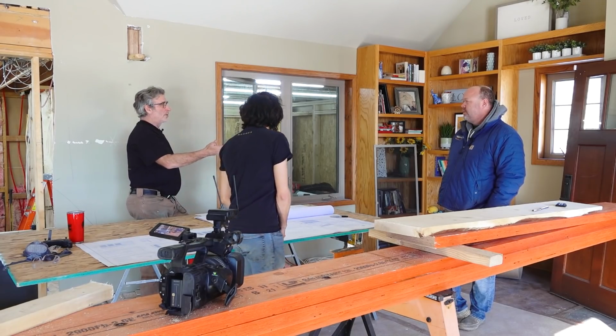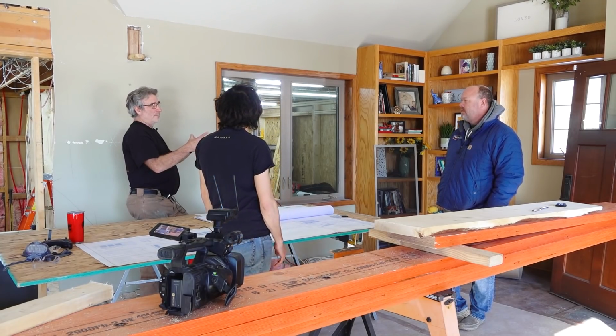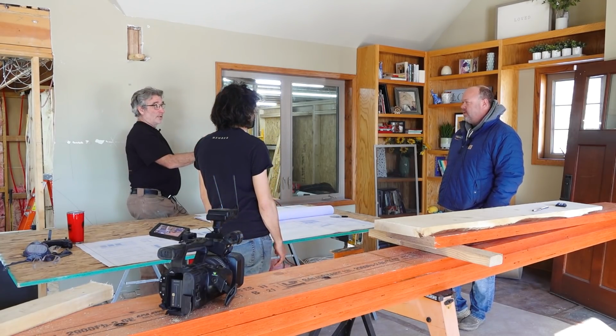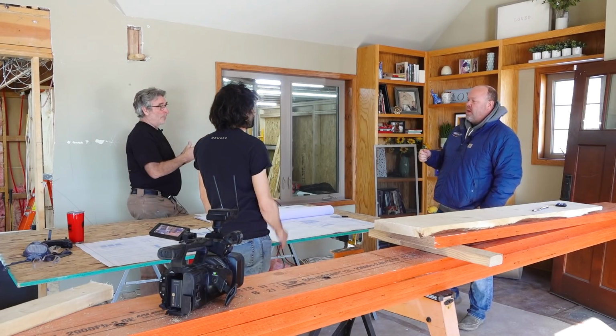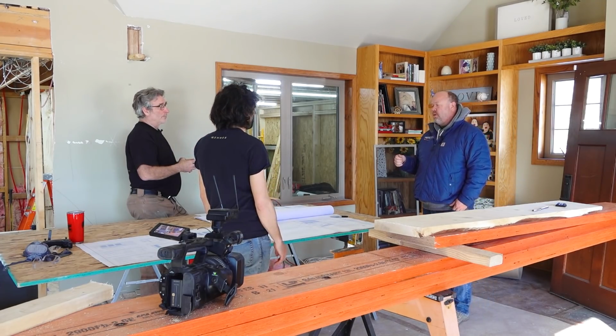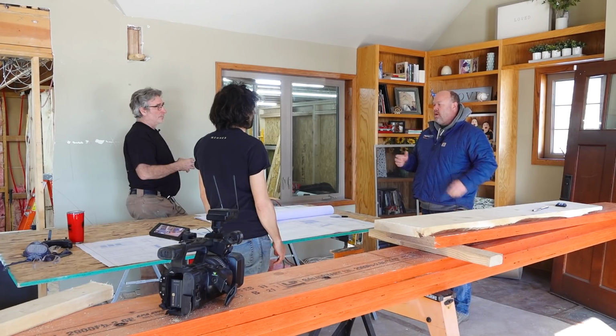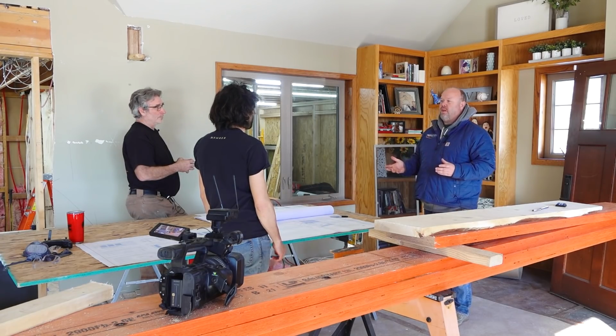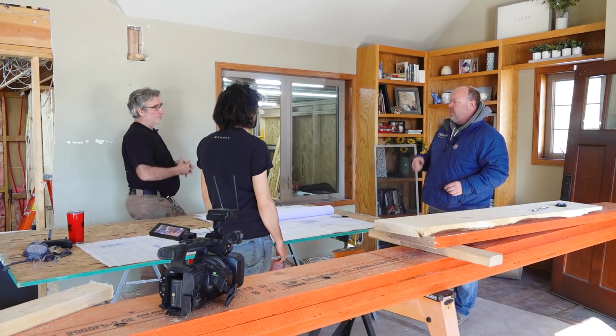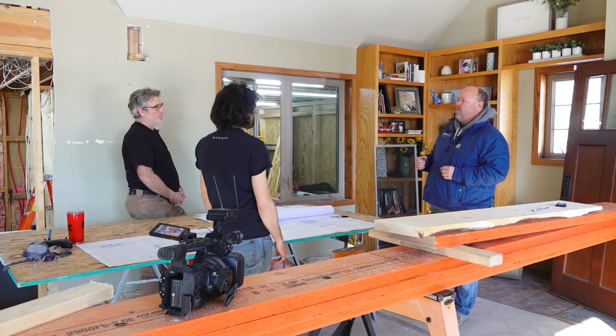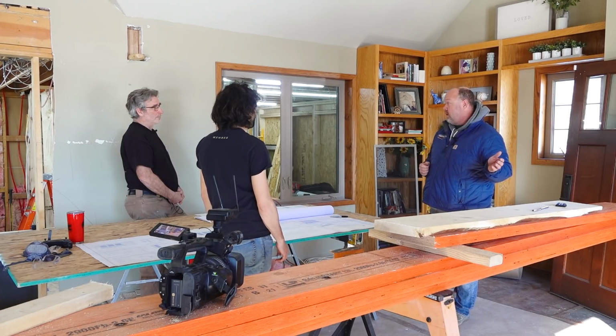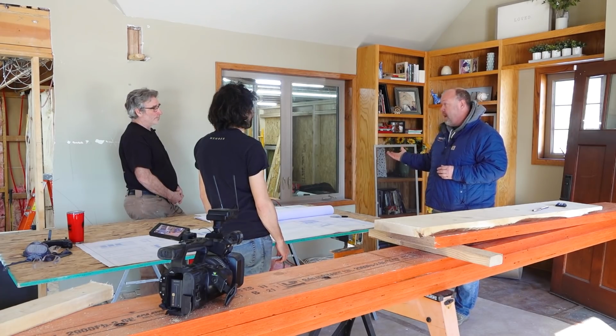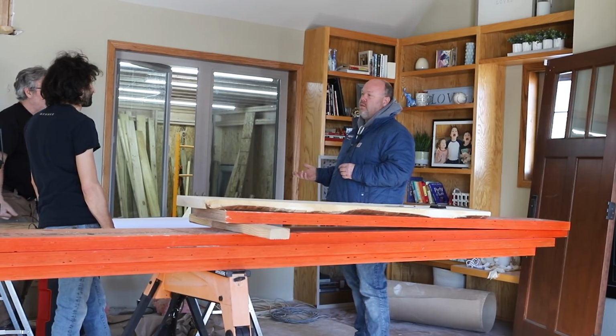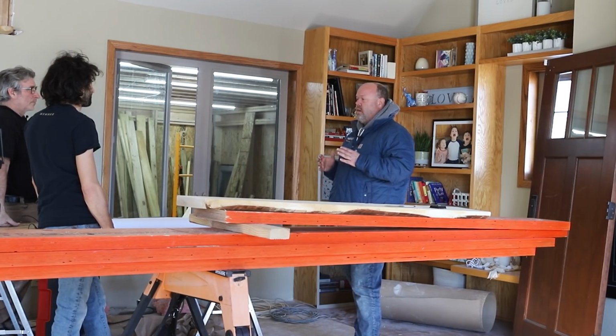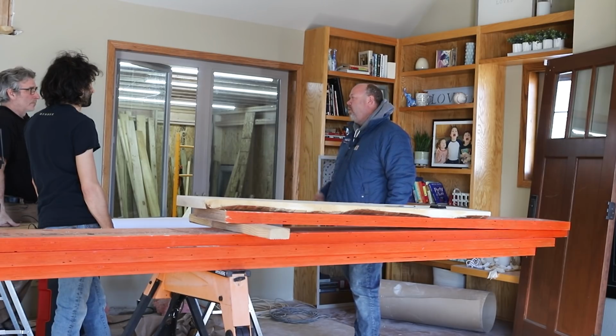The way I've seen it typically is you have fewer returns and more supplies. Yes, typically, and the reason is that our returns are bigger. We do that for a couple of different reasons. A bigger duct is going to have less velocity. Velocity is what creates air noise, so we want our returns to be a little quieter. We're not trying to throw 15 feet like a register is. We're just trying to pull back, so we don't need the velocity. So we increase the return size, and increasing the return size is going to pull more CFM.